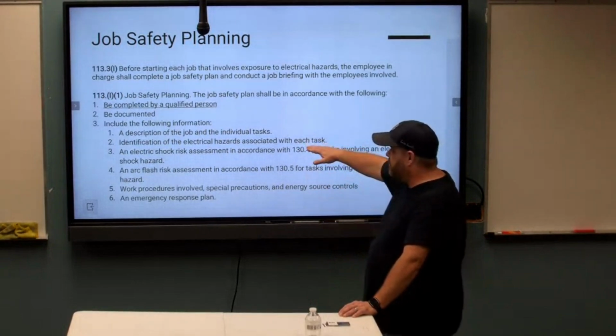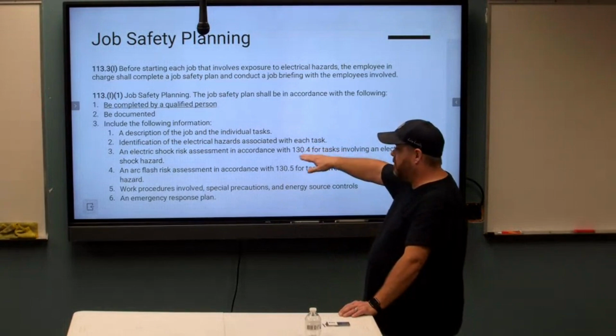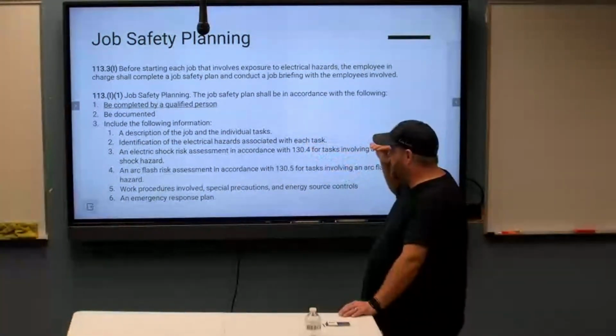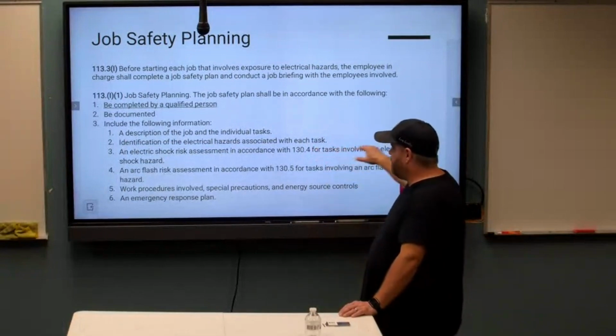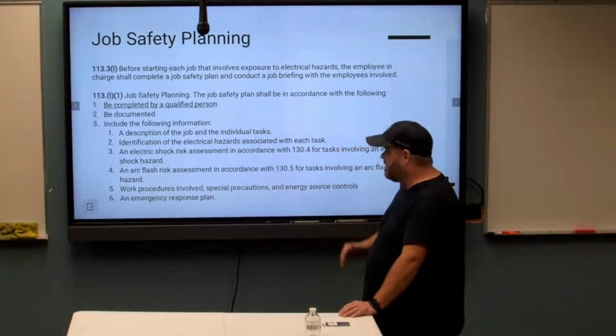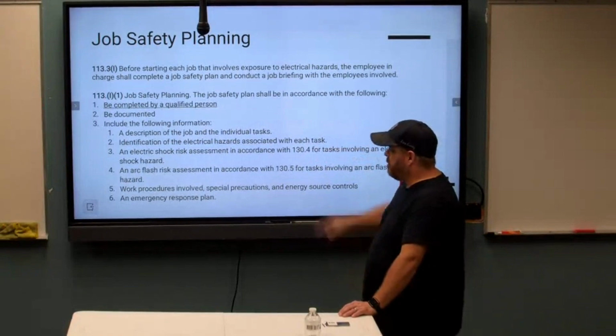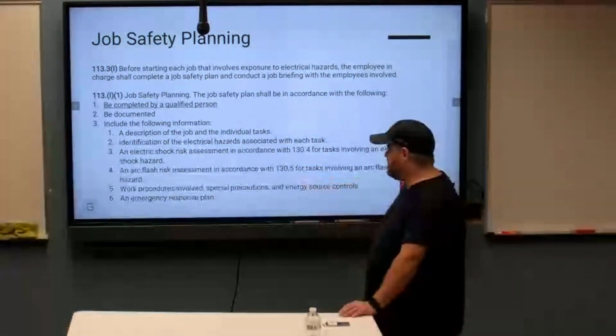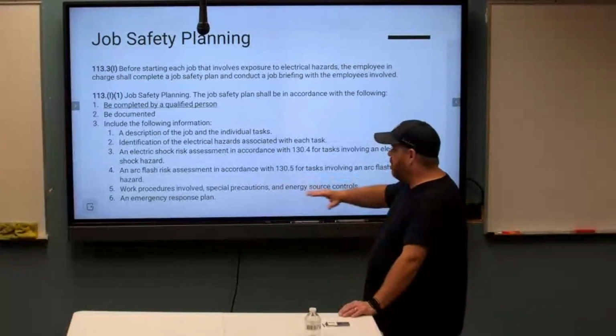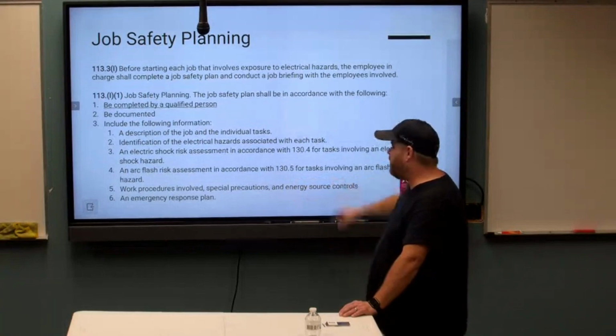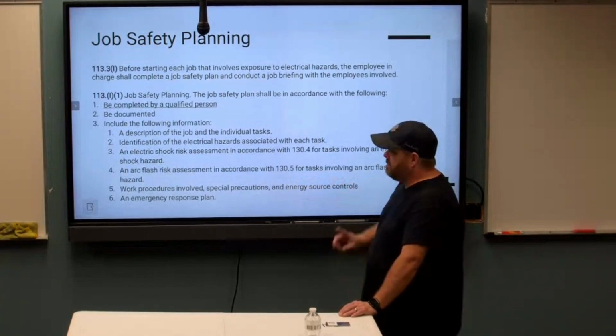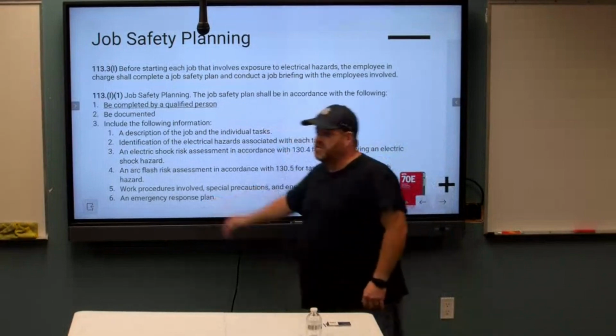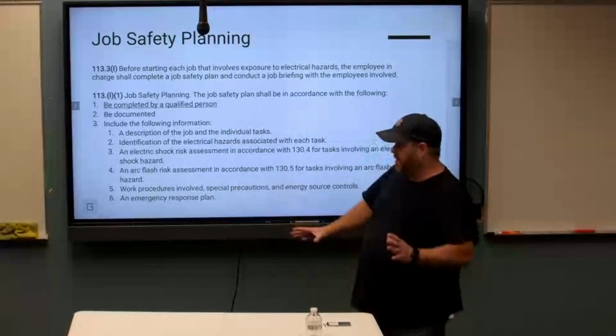We have to include the following in our documented plan: a description of the job and individual tasks each person's going to do, identify the electrical hazards with each task, perform a shock and arc flash risk assessment, plan out all the work procedures, special precautions, and identify energy source controls. And the big change this year, the 24 version of the 70E, is we have to have an emergency response plan too, documented.